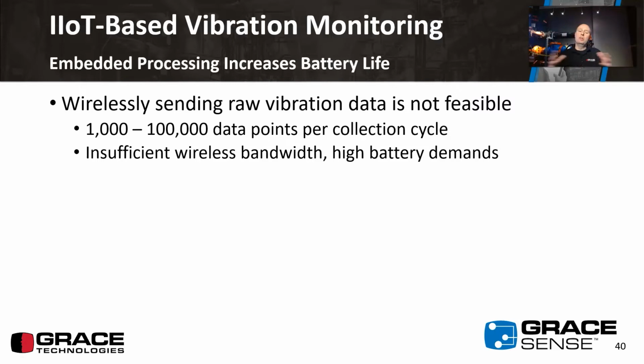So wirelessly sending raw vibration data is not feasible. Typically, to do the type of analysis we talked about earlier, you need somewhere between 1,000 and 100,000 data points collected in any one vibration cycle. So if we want to get data once per hour, I'd have to send probably around 10,000 data points every hour to do that analysis.